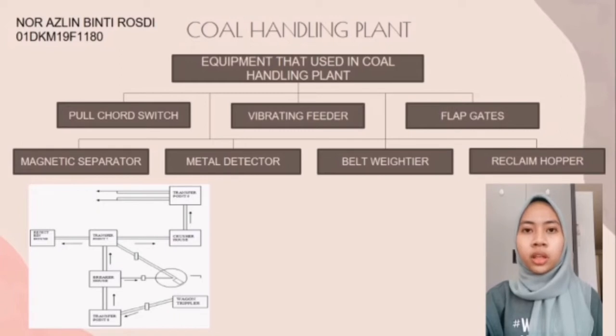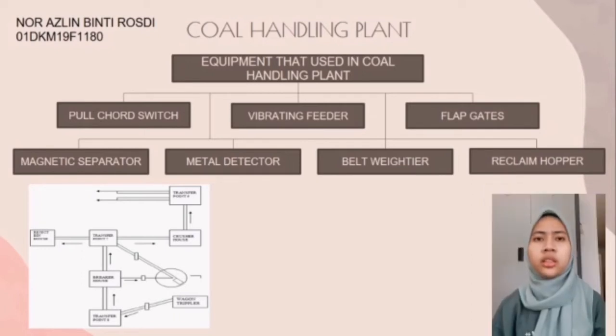Magnetic separator. These are used to separate the ferrous impurities from the coal. Metal detector. The transmitter consists of a high-frequency oscillator, which produces oscillations of 1500 Hz at 15 volts. The receiver receives this frequency signal if there is any presence of metal in the coal. Then this frequency is disturbed and a tripping signal is sent to the relay to stop the conveyor belt.